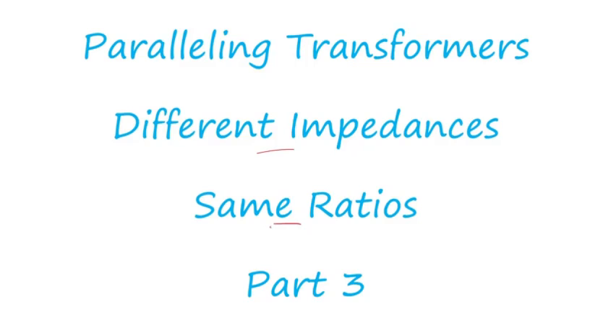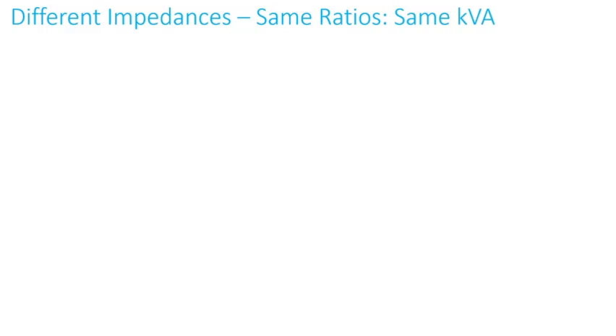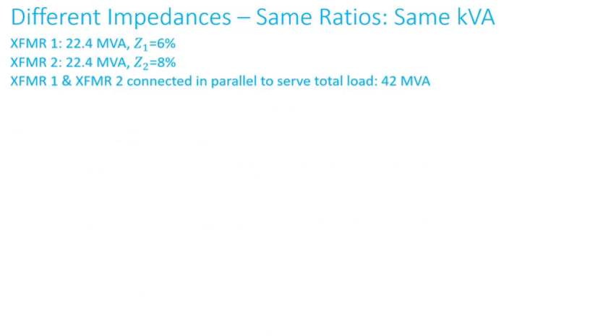In Example 1, both transformers have the same KVA or MVA. Transformer one is 22.4 MVA with six percent impedance, transformer two is 22.4 MVA with eight percent impedance. Transformer one and two are connected in parallel and they're serving a load of 42 MVA.